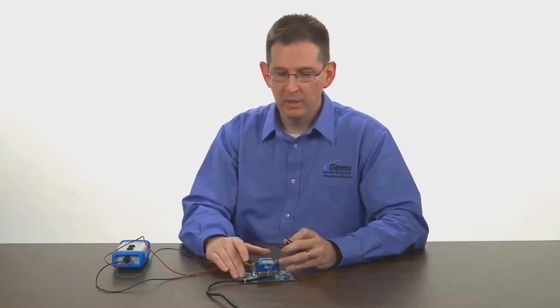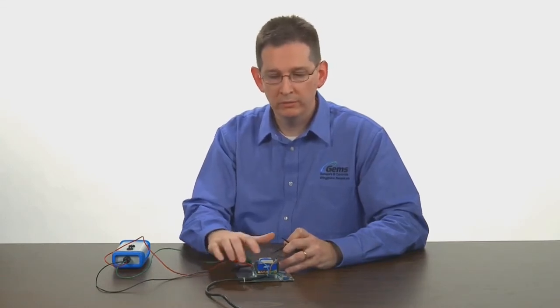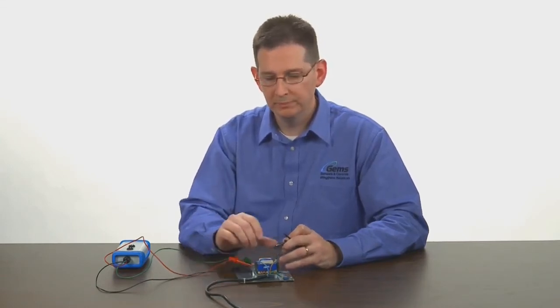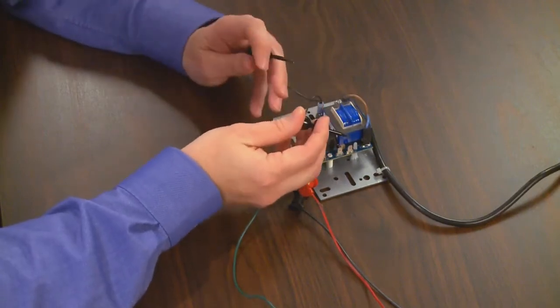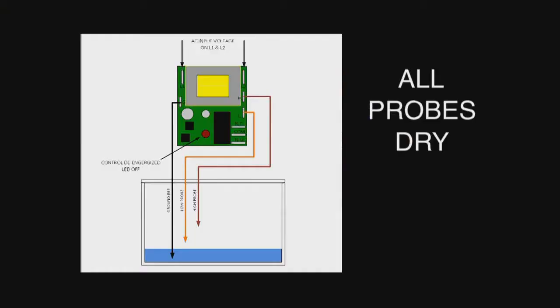The board we have is an open board Series 16 direct mode unit. The direct mode indicates that it will operate when probes become wet and de-energize when probes are dry. To do this we bring in our AC power to the two line voltages, and we use a series of jumpers to simulate either single level service or differential service.